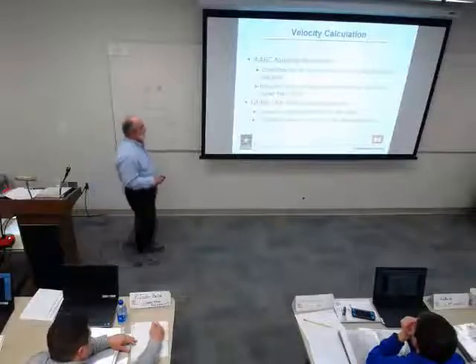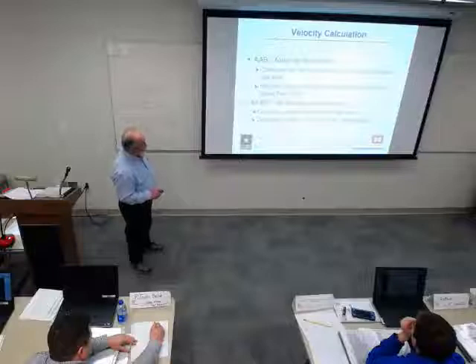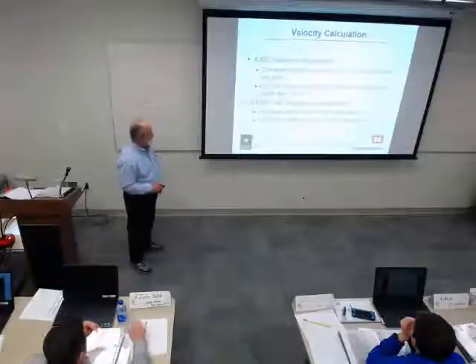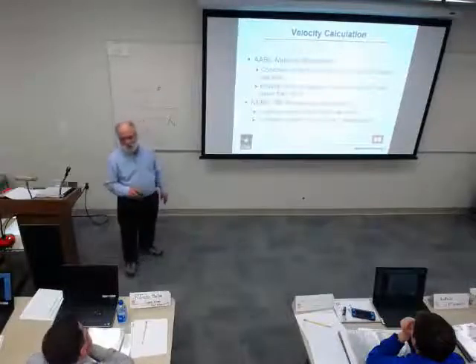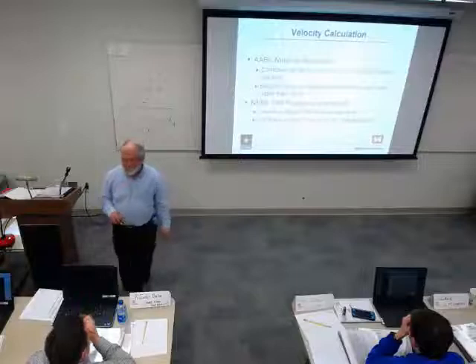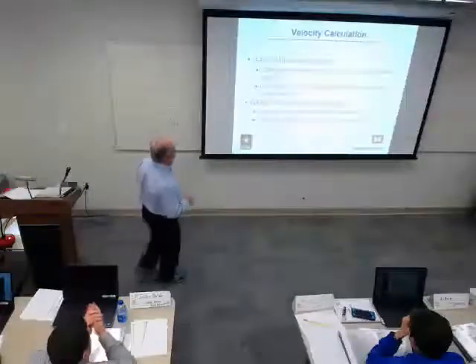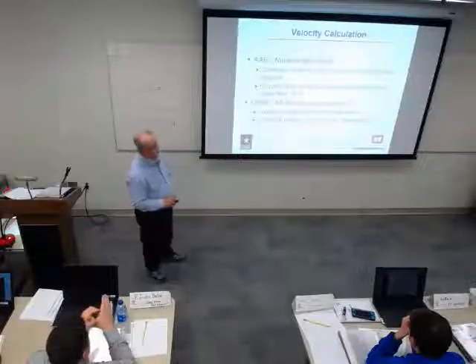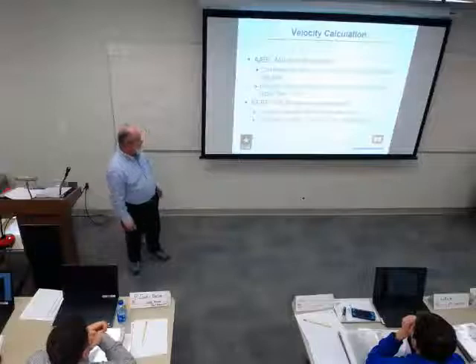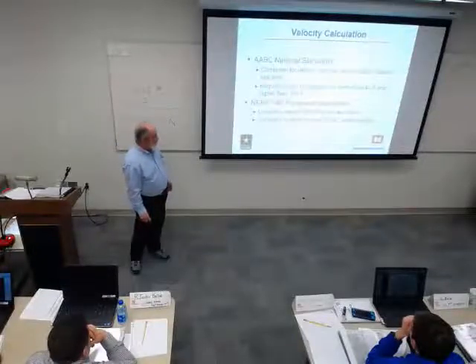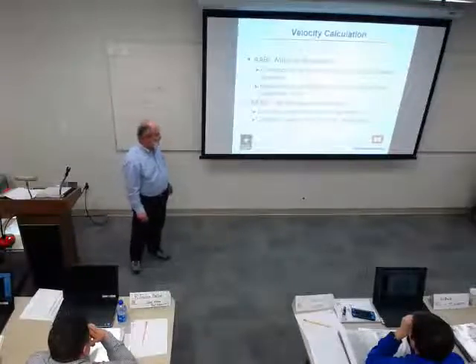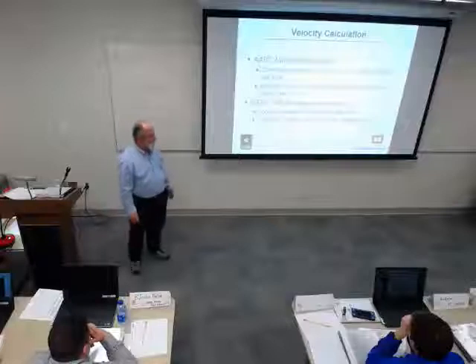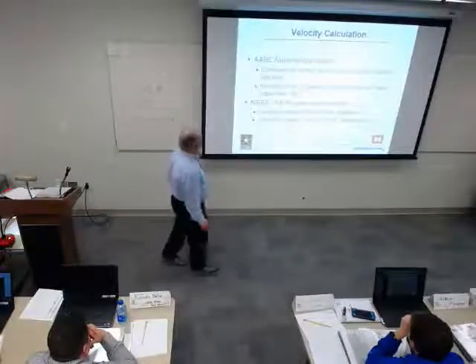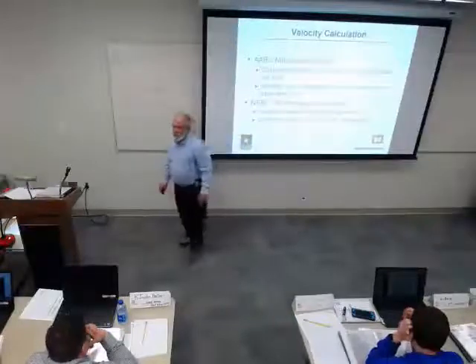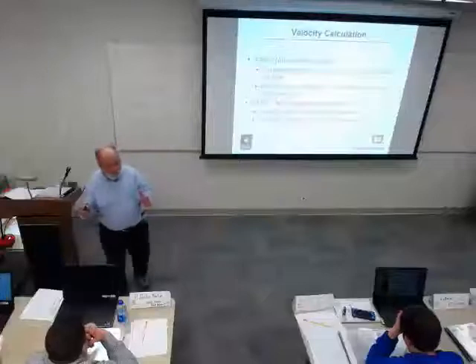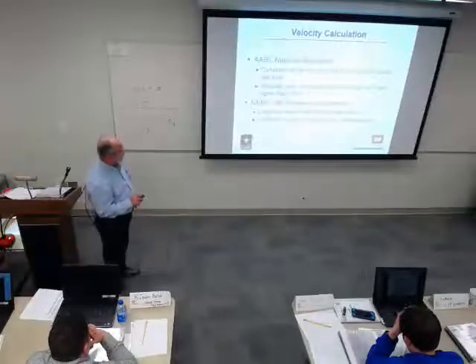The AABC national standards correct for density when you're above 2,000 feet above sea level. I believe pretty much everyone does, because on our psych charts, normally we'll use the same ones up to about 2,000 feet, and then we'll get corrected ones for over 2,000 feet. That's also required when the temperature is lower than 40 and higher than 100, because the density starts getting out of range. The NEBB standards use the same 2,000 feet above sea level, and they ask for corrections outside of the normal HVAC temperatures. So if you don't know, you can always fall back on somewhere between 40 and 100, unless your tab guy has a tighter definition of normal. Whatever is the tightest, the 40 and 100 are his.